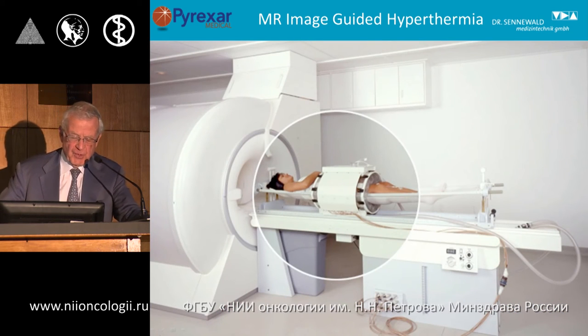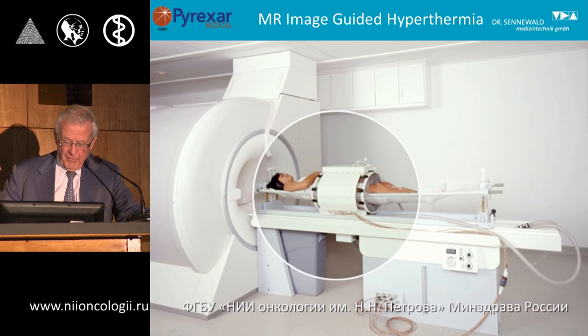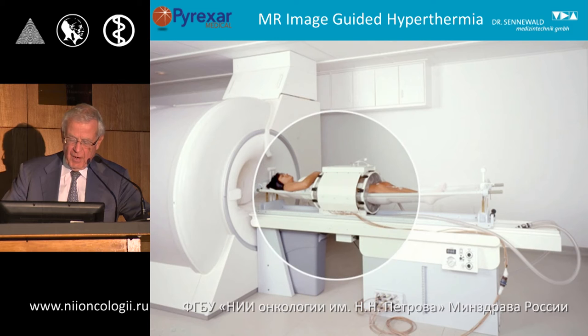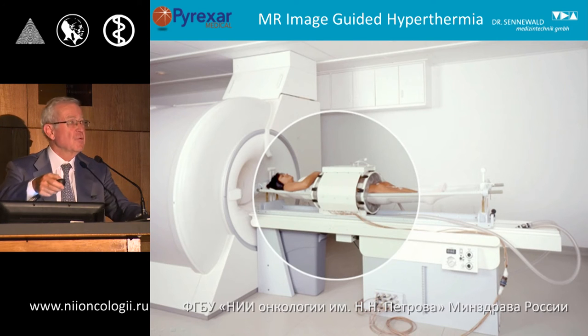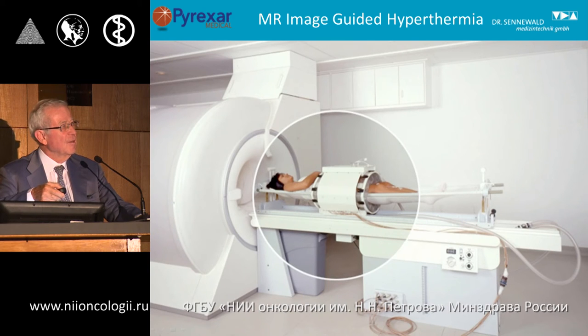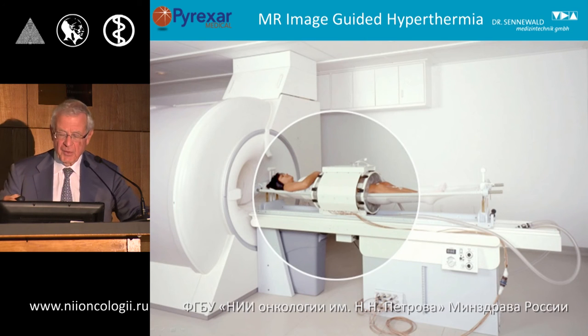This is an image of such a system, installed at Erlangen University Hospital. It shows how the system operates: a patient support system is added to the rear side of the magnet, the patient is placed inside the hyperthermia applicator, and then the entire system — patient support including the applicator — is shifted inside the magnet for treatment.